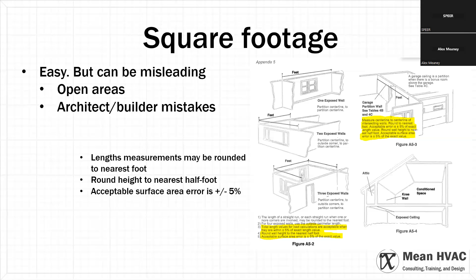I know it's the easiest thing to look at, but you'd be surprised how little difference a couple hundred square feet of wall might make to a load. So it really doesn't amount to a whole lot of importance. Obviously it needs to be in the ballpark, that plus or minus 5%, but ultra precision is definitely not necessary.